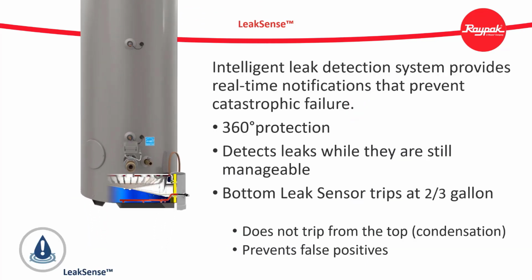The proprietary leak detection system is pre-installed on all models. It will catch all leaks, both internal and fittings on the outside, since the pan sticks out a little around the edges. The pan is built in as part of the unit. The leak cord is enclosed in a splash guard to protect it from condensation drips and false positives. This also protects the leak detection cord from minor splashes resulting from expected kitchen washdowns.